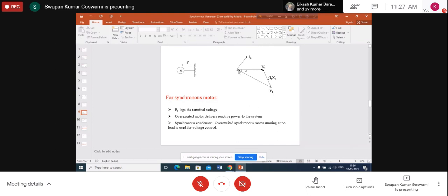That means when the demand is heavy, somebody should supply reactive power. When the demand is low, reactive power need not be supplied. So by changing the field current of the motor, you can use it as a source of reactive power. This application of the synchronous motor is of interest to power systems, because the synchronous motor may be used as a source of reactive power.